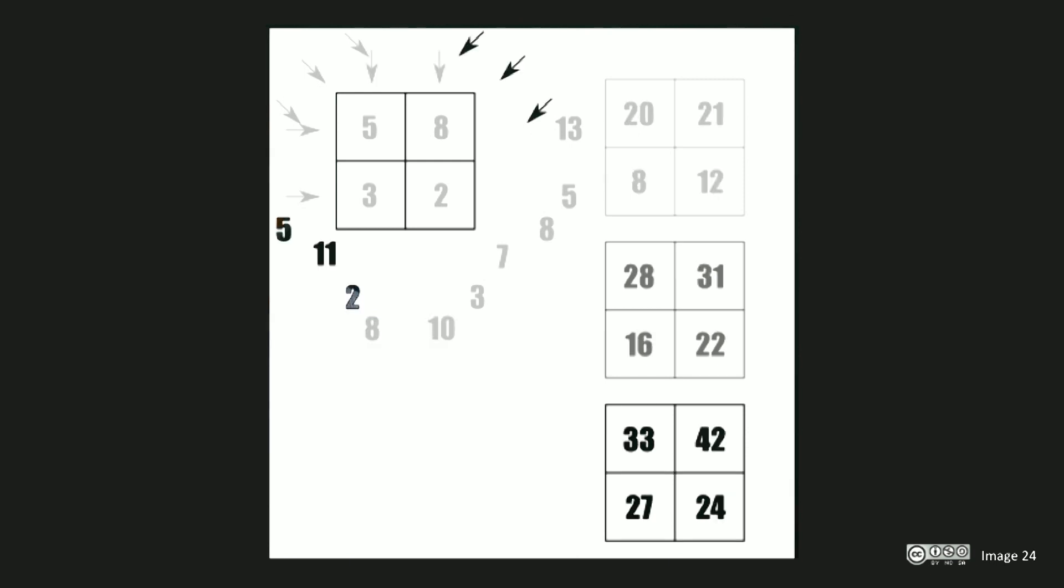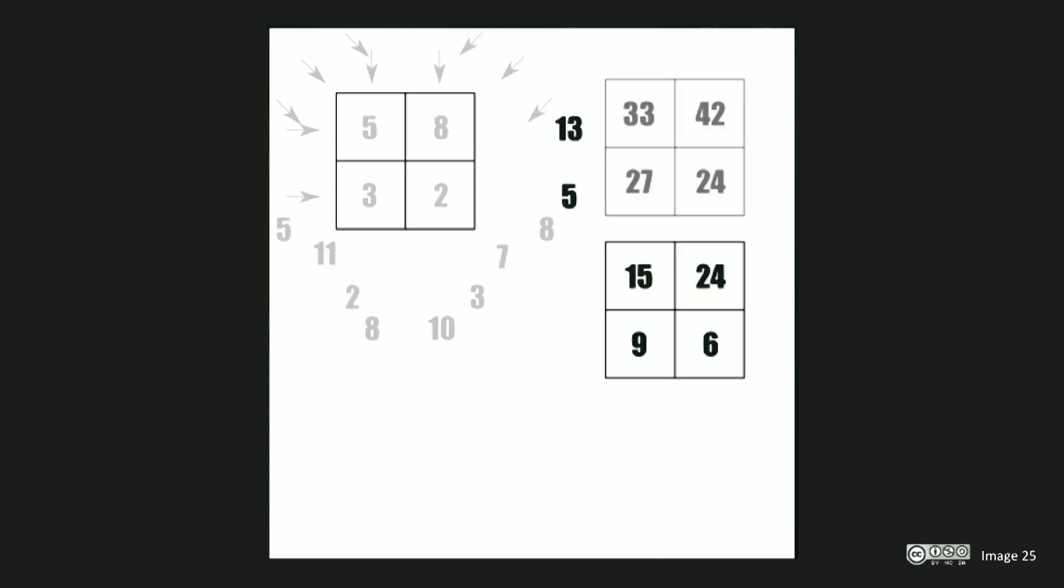We then go back to the first projection and subtract the sum of this projection, in our case 13 and 5, resulting in 18, from each of the elements of our current projection. This gives us a new block of 15, 24, 9 and 6. The final step is then to divide by the number of remaining projections, in our case 3, to give us our final result that matches our original data.